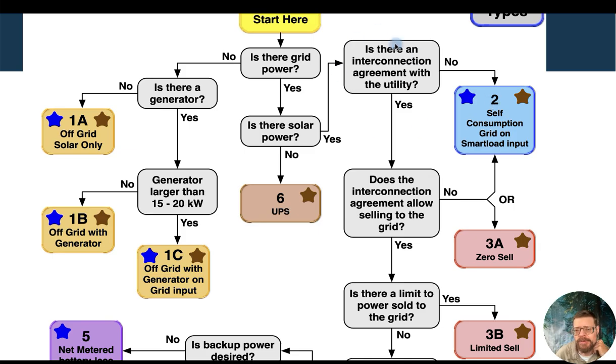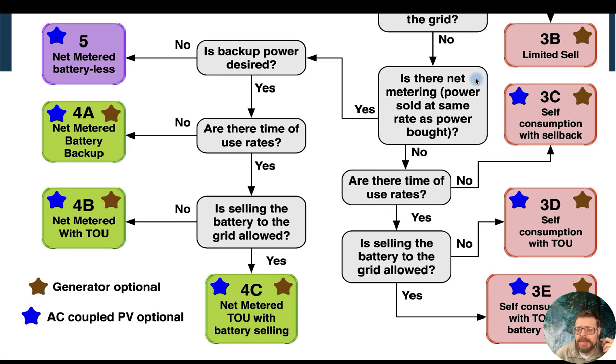If we do have an interconnection agreement with the utility, then we get into a whole series of questions. Does it allow selling to the grid? How much does it allow selling to the grid? Going down farther, do we have net metering, are there time of use rates, and are we allowed to sell battery power to the grid or just solar power? If we have net metering, we go through a bunch of those same questions. There's also the question: do we want batteries or not? Most of the time our inverter is used with batteries, but it is also possible to use it just as a straight grid-direct inverter.